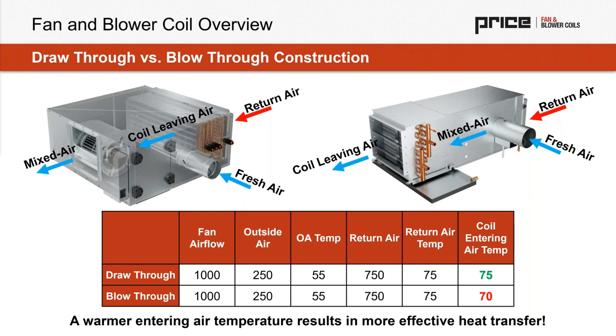degrees. Now, when we look at the product on the left, that return air is essentially going to be hitting the coil directly, 75 degree air, 750 CFM. And that means we're going to have a more elevated entering air temperature into the coil. The one on the right, we're going to see 750 CFM at 75 degrees mixed with 55 degree, 250 CFM air for 70 degrees and 1000 CFM total. So a greater overall mass, but a lower entering air temperature, which means that coil is going to run a little bit less efficiently. This is opposite for heating.